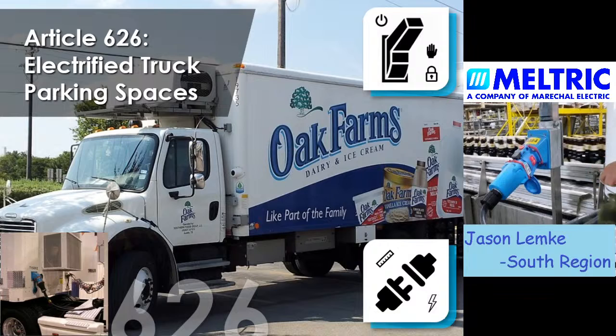Suppose it's a motor and you want to do your disconnecting means right there at the motor, lock it out, tag it out, follow all your electrical safe working procedures, and then be able to do whatever you need with the motor and put it back into service by plugging it back in. So that makes it a lot more efficient. It keeps you in compliance with things like line of sight disconnects. It keeps you in compliance with lockable, and it can really help you make your lockout tagout procedures a lot more efficient. So that's kind of where we would see a little bit about where to use plugs and receptacles.